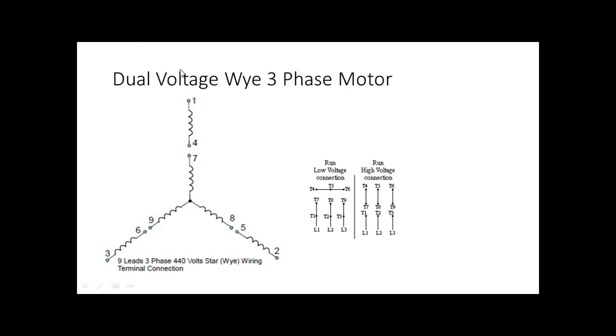So according to this, if I'm going to wire it for low voltage, it says I need to put a jumper between 4, 5, and 6. So just use some short jumpers and jump 4, 5, and 6. Then I need to put a jumper between terminal 1 and 7, a jumper between terminal 2 and 8, and a jumper between terminal 3 and terminal 9.